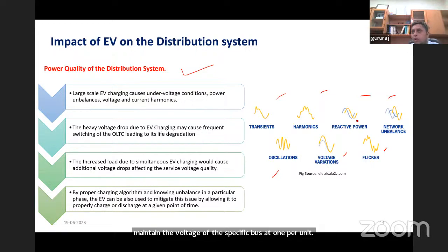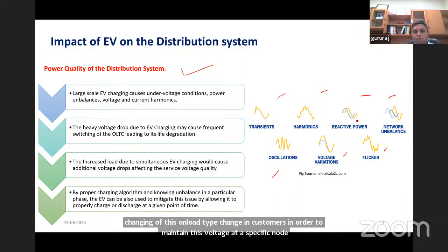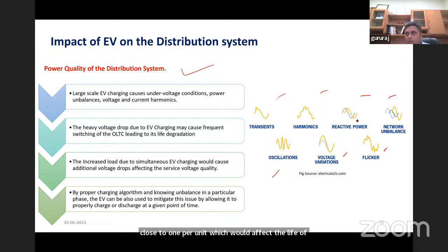But most on-load tap-changing transformers are mechanically driven, manually operated, and it can happen that there is frequent switching of the tap changer in order to maintain voltage at a specific node close to 1 per unit. This affects the life of these on-load tap-changing transformers, which have a limited life. Because electric vehicles are brought in frequently and charged simultaneously, this affects transformer life. So we need to look into this and ensure on-load tap-changing transformers do not get overburdened as we bring in multiple electric vehicles across various distribution systems.